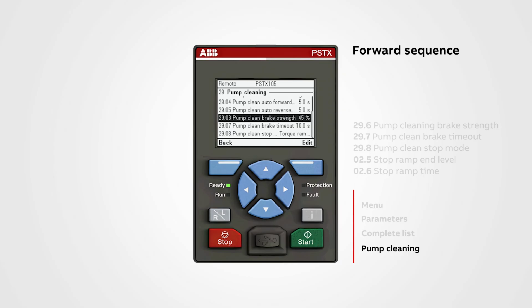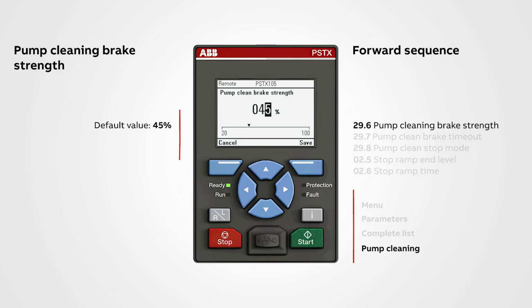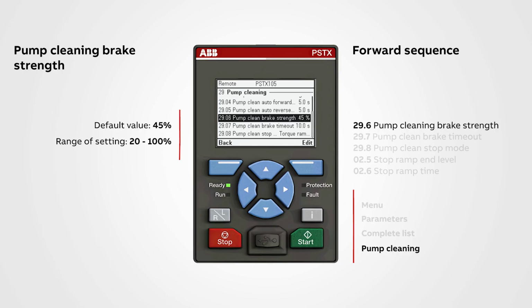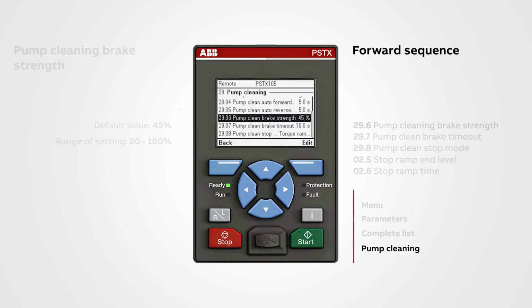The next parameter to set is the 29.6, pump cleaning brake strength. This parameter will set the pump cleaning braking strength, where the default value is 45%. The range of this setting is between 20 to 100% strength. With a lower value, the softer the brake will be, and a higher value will make the pump stop faster. However, the pump cleaning braking function will only be activated in the forward direction stop sequence.